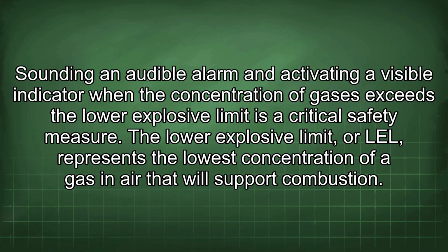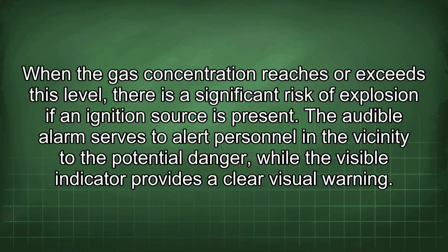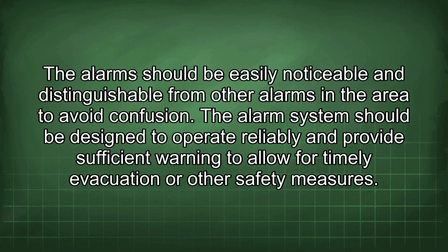Sounding an audible alarm and activating a visible indicator when the concentration of gases exceeds the lower explosive limit is a critical safety measure. The lower explosive limit, or LEL, represents the lowest concentration of a gas in air that will support combustion. When the gas concentration reaches or exceeds this level, there is a significant risk of explosion if an ignition source is present. The audible alarm serves to alert personnel in the vicinity to the potential danger, while the visible indicator provides a clear visual warning. The alarms should be easily noticeable and distinguishable from other alarms in the area to avoid confusion.